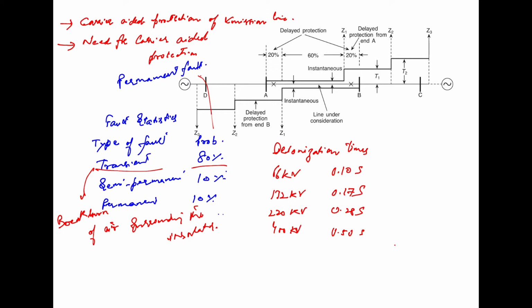Now, whenever the fault takes place, we can tentatively assume that a transient fault has interrupted the supply, and then we wait for a short while before switching on the circuit breaker, and this is known as the reclosure. This reclosure can be carried out manually or automatically, and if the fault was indeed a transient one and the interruption was of a duration greater than the deionization time, then the reclosure would be successful. That is, there would be no reoccurrence of the fault.